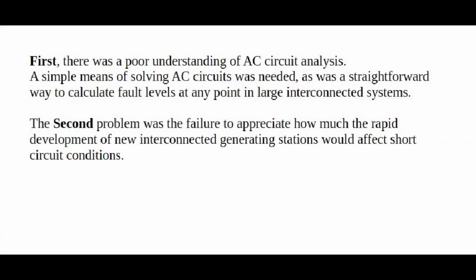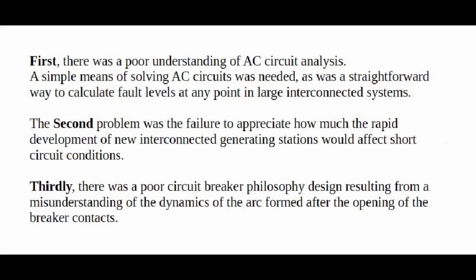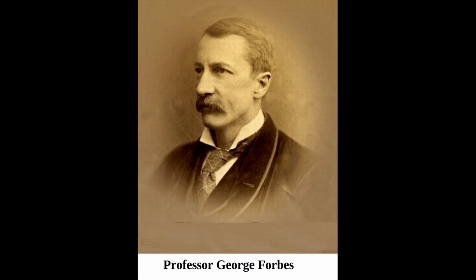The second problem was the failure to appreciate how much the rapid development of new interconnected generating stations would affect short-circuit conditions. Thirdly, there was a poor circuit breaker philosophy design, resulting from a misunderstanding of the dynamic of the arc formed after the opening of the breaker contacts. There was also a problem of overvoltage caused by a short circuit. This problem had been noted in the late 1880s by Professor George Forbes, but he, like everyone else at the time, had no idea what was going on. Forbes was a well-respected electrical authority who had produced the preliminary Niagara alternating design.